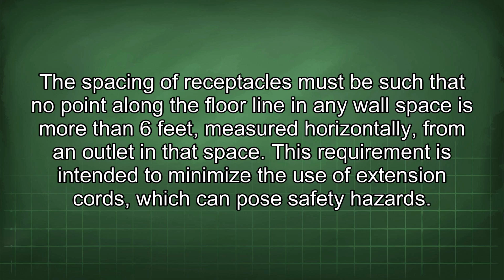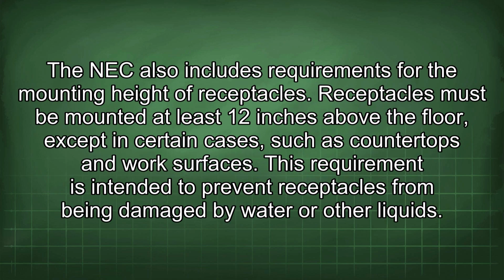This requirement is intended to minimize the use of extension cords, which can pose safety hazards. The NEC also includes requirements for the mounting height of receptacles. Receptacles must be mounted at least 12 inches above the floor, except in certain cases such as countertops and work surfaces. This requirement is intended to prevent receptacles from being damaged by water or other liquids.